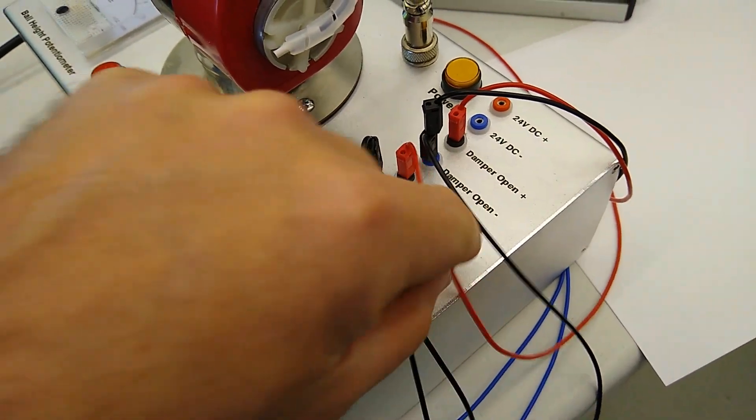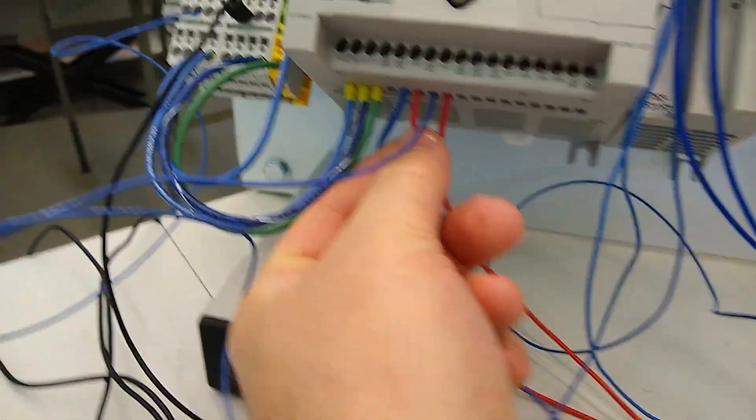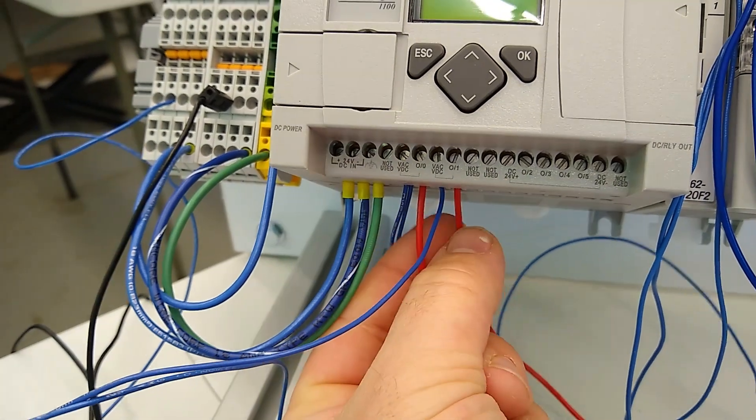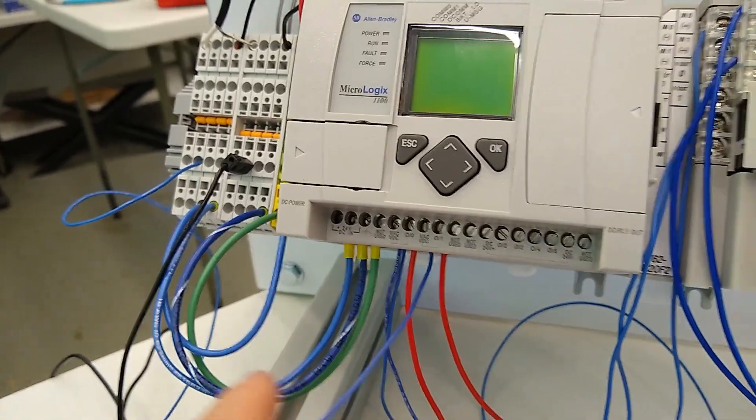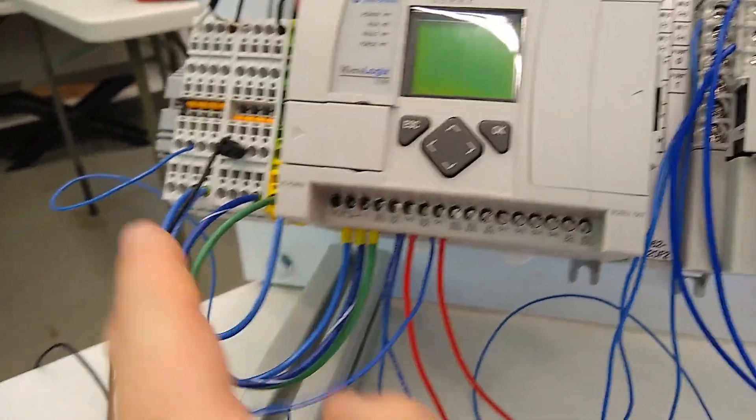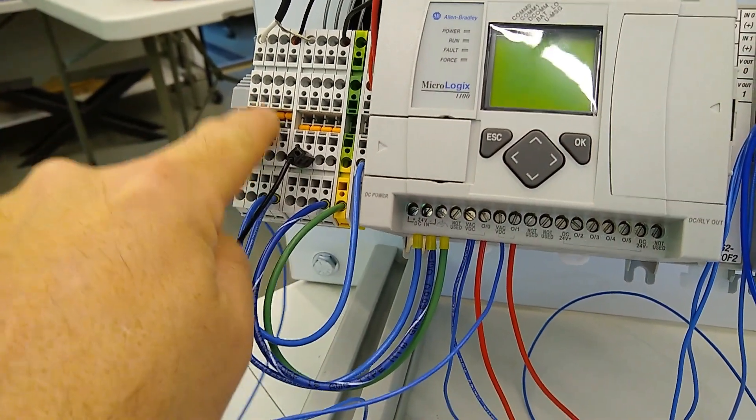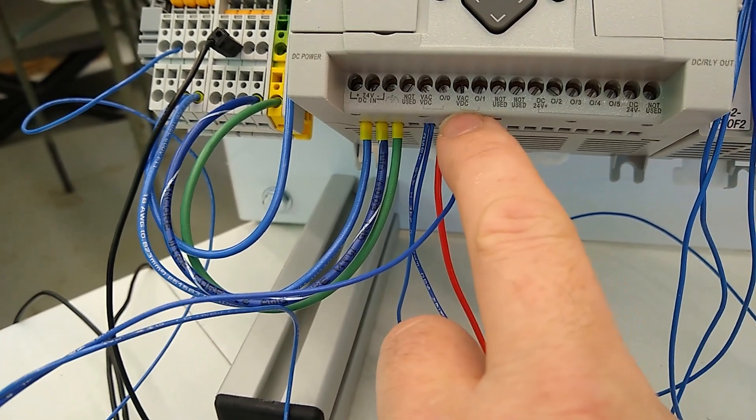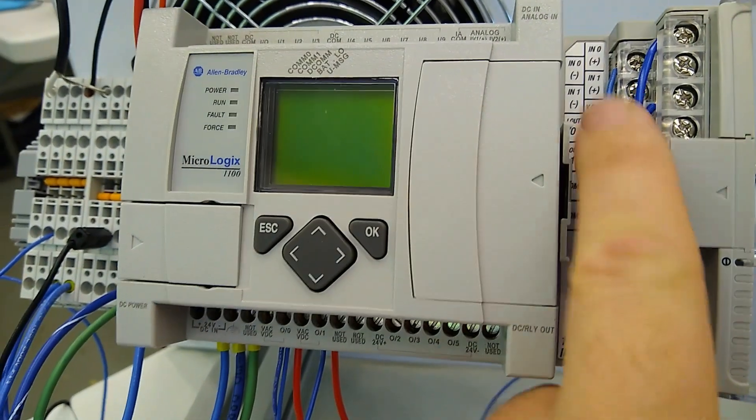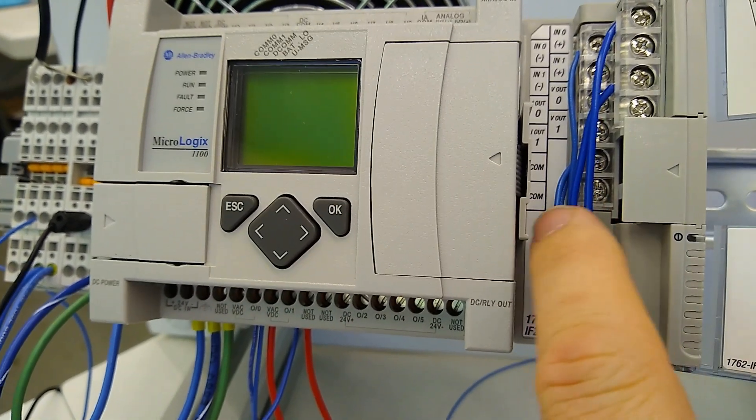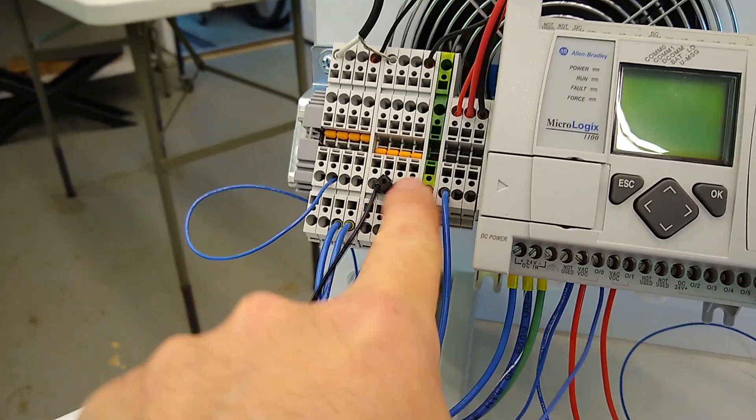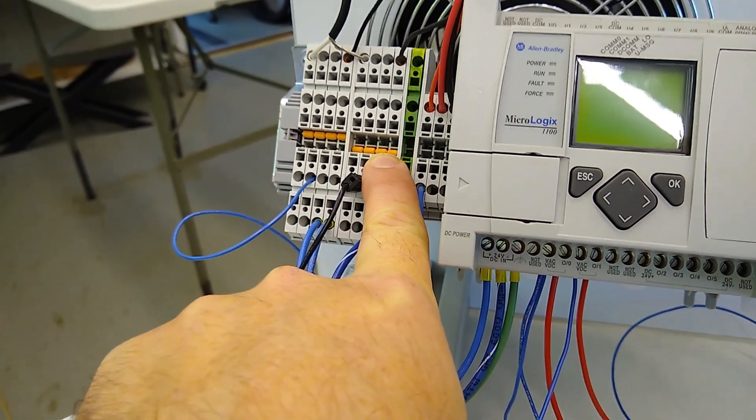And then we have damper open and damper close. Damper open is going to go to output zero and damper close is going to go to output one. Also a few additional wires that you need on the MicroLogix 1100 is we have plus 24 volt, which is our left set of terminals connected to the VDC terminal for output zero and the VDC terminal for output one. And also right here, you need to connect the IN0 minus to your com, and that will connect on to the left side of terminals, which is our zero volt of our power supply.